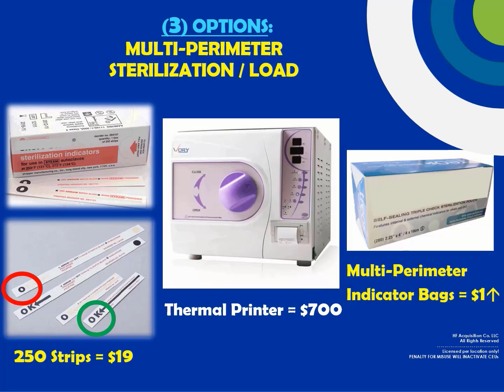An alternative to using strips is to use a thermal printer. Many heat sterilizers are pre-built to accept printout roll tape, or you can purchase an external thermal printer. Most are priced at $700. You can purchase multi-parameter sterilization pouches. Their cost is approximately $1 more per box than traditional pouches. Keep in mind that traditional pouches only change color when sterilizer temperature is met. Multi-parameter pouches will change color only after time, temperature, and pressure measures have all been met.